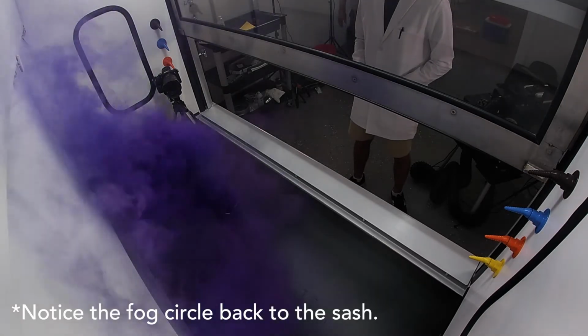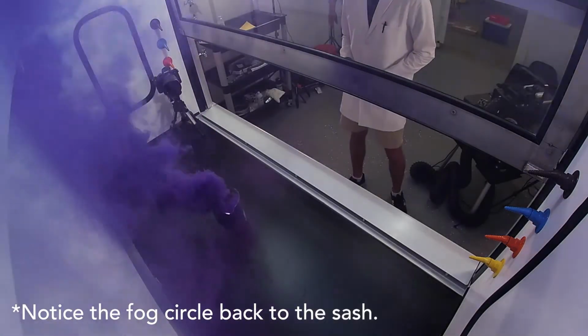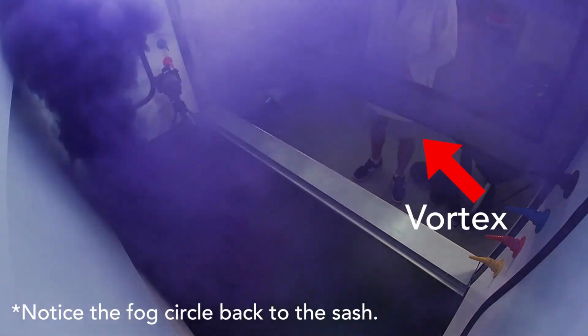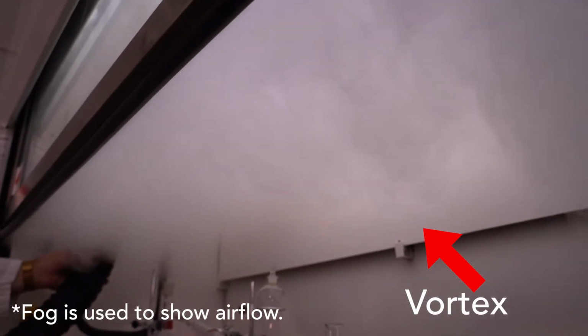While the sash provides protection, it is also a potential source of hazard. There can be contaminated air present at the edge of the sash. There can be a vortex of contamination just behind the sash. These vortices have the highest concentration of contaminants.